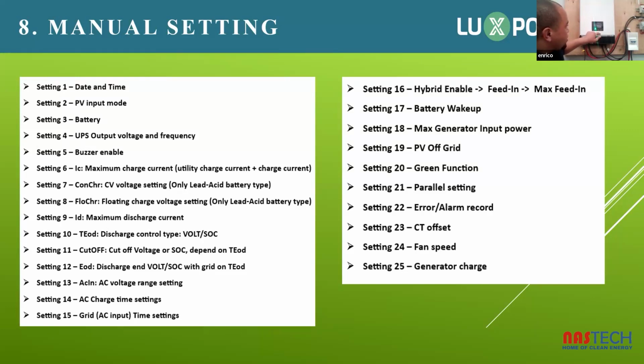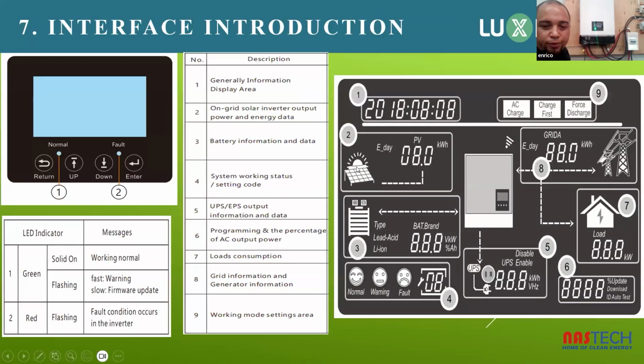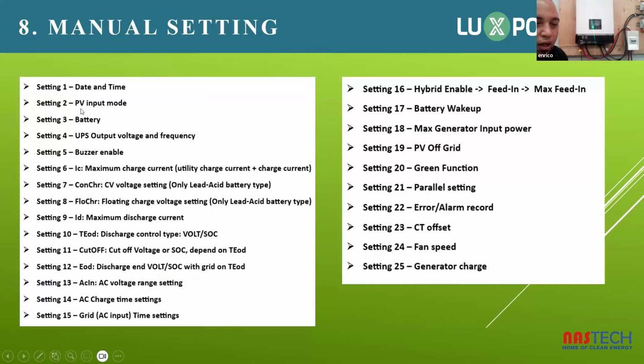The next setting is your solar panel setting. You'll go up to number 2, and this area will flash on the inverter to show that you are busy with this area. Then you tell the inverter whether you have one string coming from the solar panels, or you have 2 strings on top of your roof, and you will make use of both MPPTs.